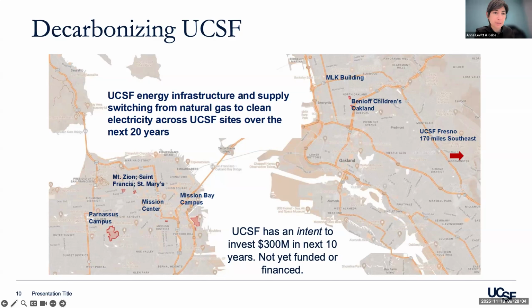For sites beyond Parnassus that don't have cogeneration, the overall intent is to use heat recovery chillers and creative ways to both absorb and reject heat to keep things balanced, possibly with thermal energy storage, supplemented by air source heat pumps for most heating. We're exploring geothermal potential at our MLK building, and last year's decarbonization study identified potential in Oakland for recovering municipal sewer heat through heat pumps — a consideration for a partnership with the city of Oakland.